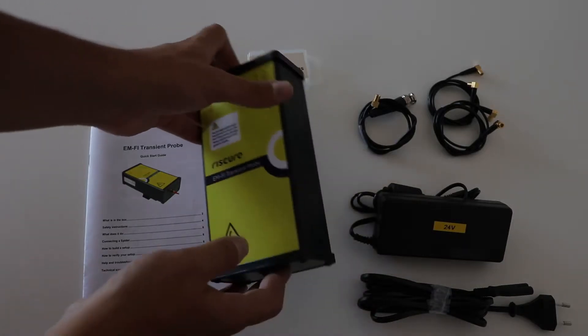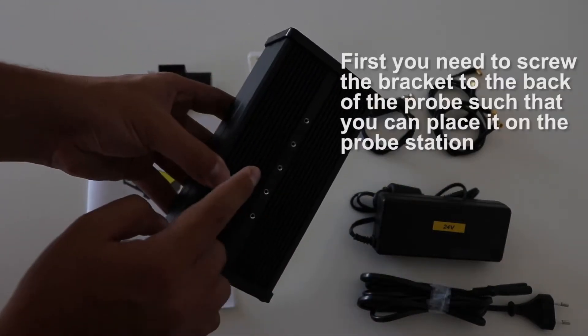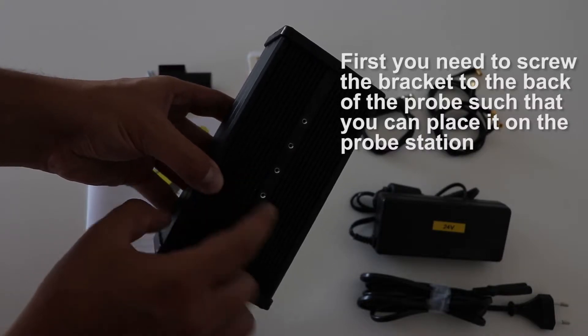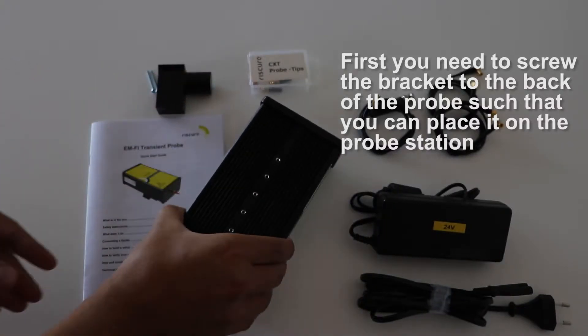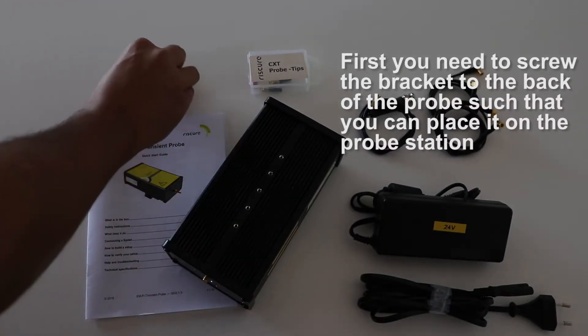The first thing you need to do is to assemble the bracket to the back of the transient probe. That way, you'll be able to place the probe to the probe station.